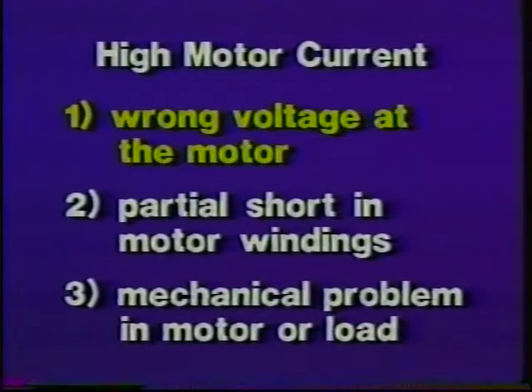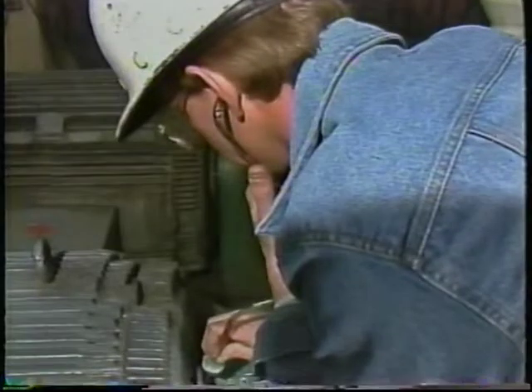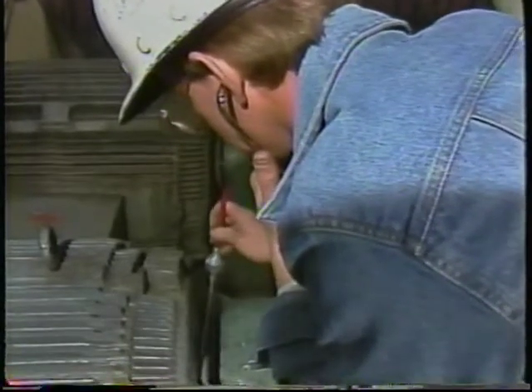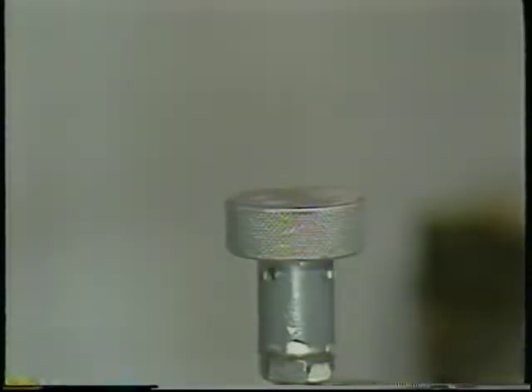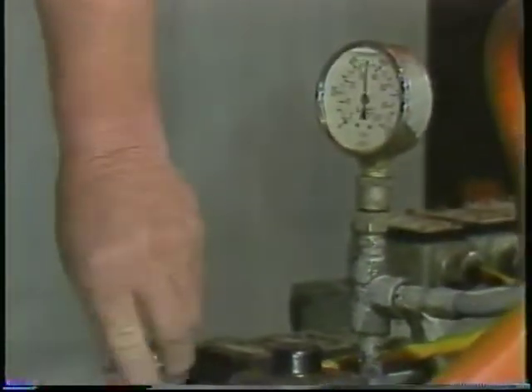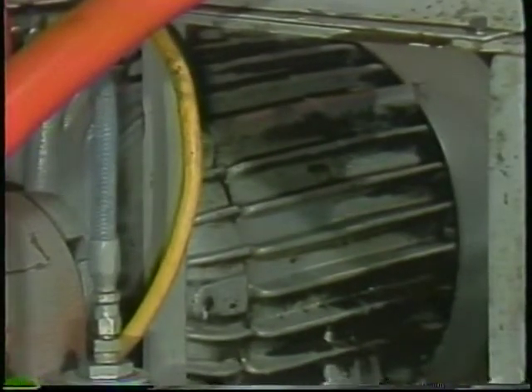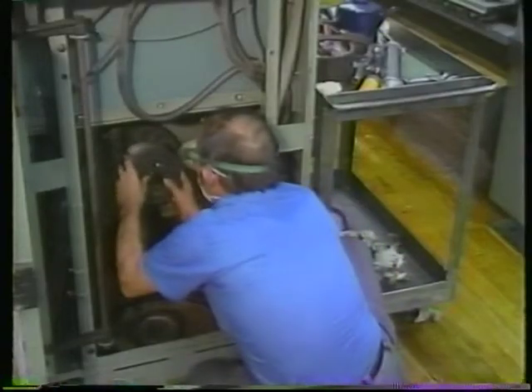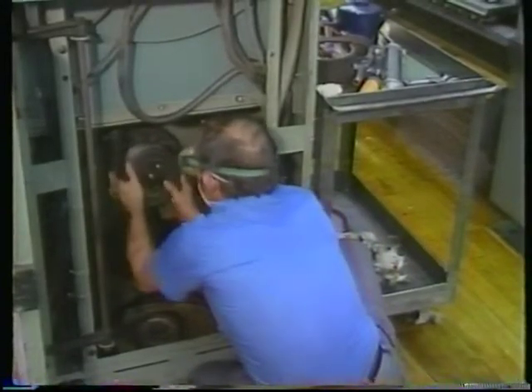If none of your electrical tests indicate anything wrong with the motor, chances are pretty good that you have a mechanical problem in the motor or the load. Check for bad bearings and other possible sources of high friction. Be suspicious of any change or adjustment recently made in the load. Remember that changing a flow control or pressure relief valve setting will affect the motor driving a pump. Any ratio change in a drive will change the load on the motor. And centrifugal blowers may overload their motors if certain ductwork or filters are removed or damper settings are changed.